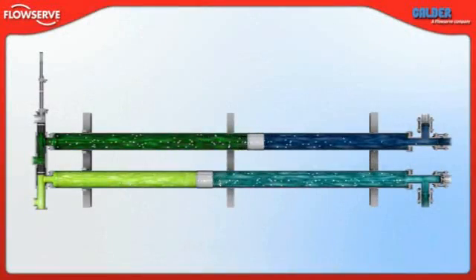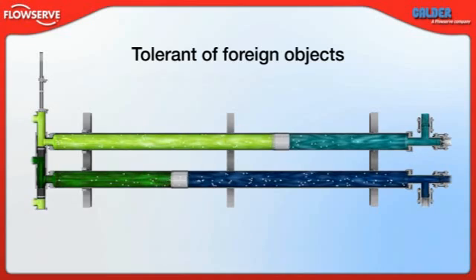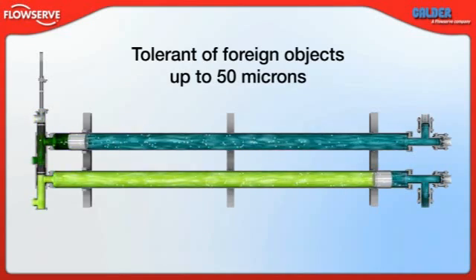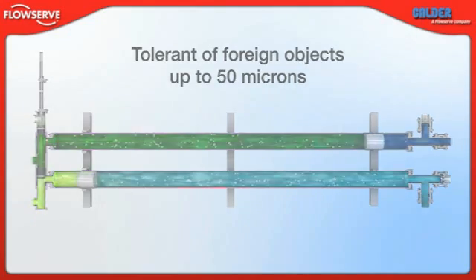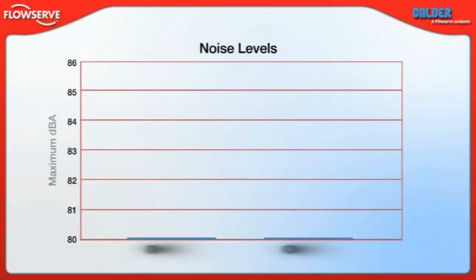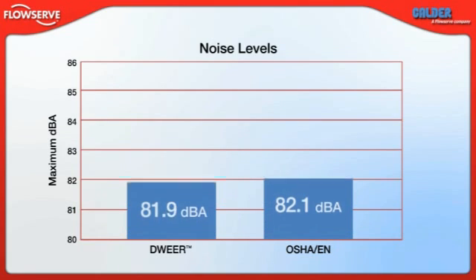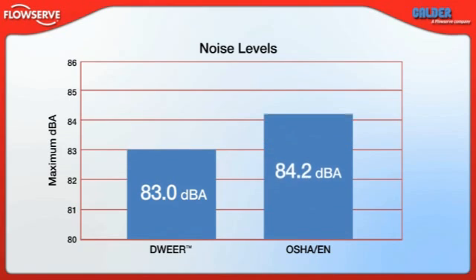Third, the DWEER is extremely tolerant of foreign objects. It can pass objects up to 50 microns, so special flushing procedures and costly strainers and filtration systems are not needed. Finally, the DWEER is a quiet machine. Because of its slow operating speed — about 5 cycles per minute — it generates less than 83 decibels during operation. This is below the OSHA and EN threshold of 85 decibels, so noise abatement measures such as noise hoods are not needed.